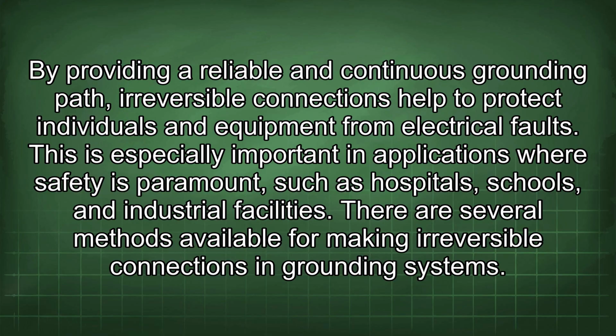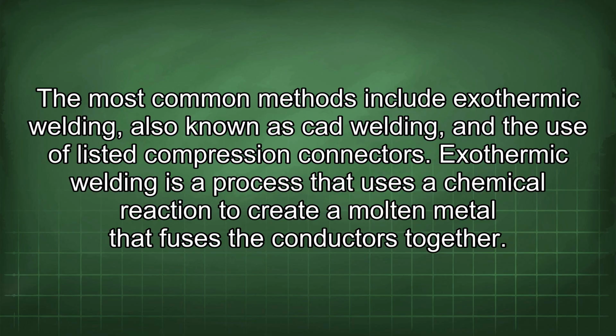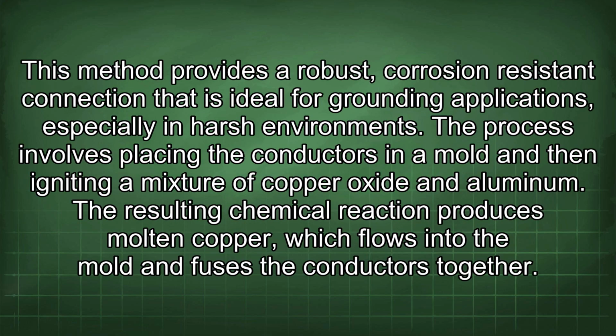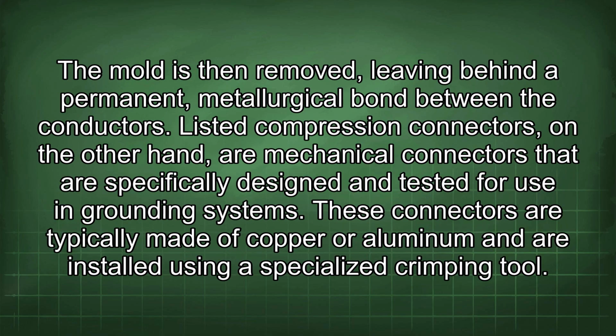There are several methods available for making irreversible connections in grounding systems. The most common methods include exothermic welding, also known as CAD welding, and the use of listed compression connectors. Exothermic welding is a process that uses a chemical reaction to create a molten metal that fuses the conductors together. This method provides a robust, corrosion-resistant connection that is ideal for grounding applications, especially in harsh environments. The process involves placing the conductors in a mold and then igniting a mixture of copper oxide and aluminum. The resulting chemical reaction produces molten copper, which flows into the mold and fuses the conductors together. The mold is then removed, leaving behind a permanent, metallurgical bond between the conductors.